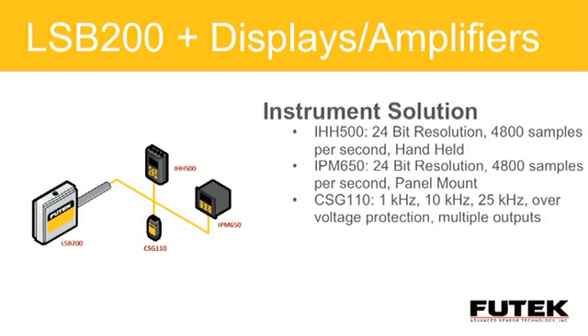With the amplifier, you can get voltage output or current output. Do you need that 4 to 20 milliamp output? The nice thing about FUTEK offering not only the load cell but also the instruments is that we can perform a full calibration for you. We can marry the display and the load cell together, give you a certificate of calibration, and you're off and running. You don't have to worry about setting this up yourself, soldering, or making connections. You get the turnkey system with the certificate if you order it.